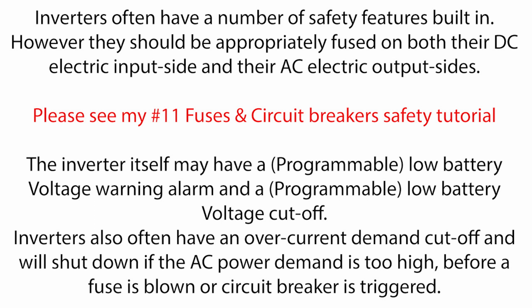Many inverters also have fuses built into them. Sometimes these fuses are easily accessible and sometimes not so easily accessed, but all in all, most if not all inverters have safety features built into them so that they are not damaged by being overloaded. But that doesn't mean you shouldn't use fuses on the outside, external fuses.